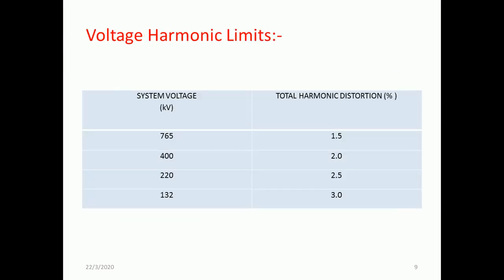Now we'll also discuss the harmonic limits. If we again speak about a 132 kV system, the permissible THD, total harmonic distortion, is 3% and should not rise above 3%. These are certain standards which have been laid down. To study the harmonic limits in detail, you can also refer to IEEE standard 519.